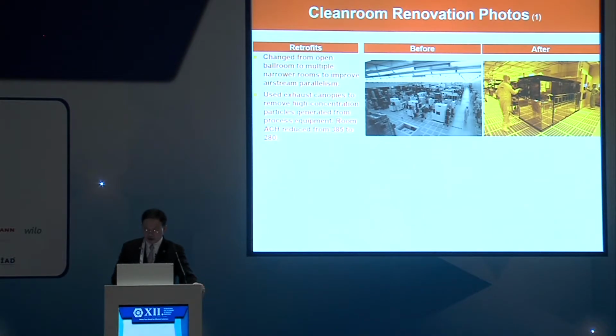And in the old design, they don't have a real exhaust system. When particles are generated in the space, they just use dilution, bringing more air to dilute. But the new design has a canopy exhaust. Once they identify the major sources of particle generation, instead of letting the particles migrate, they capture them, then use a HEPA filter to block the particles, so on the downstream side, you can still recover the air as return air. So in this case, the air change rate at the beginning was 385, down to 280, almost 100 air changes per hour reduction. So you can tell how much energy is being saved.